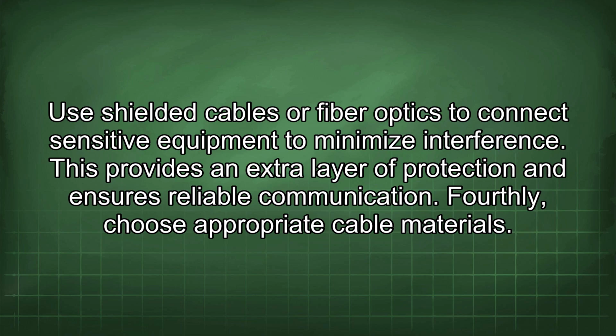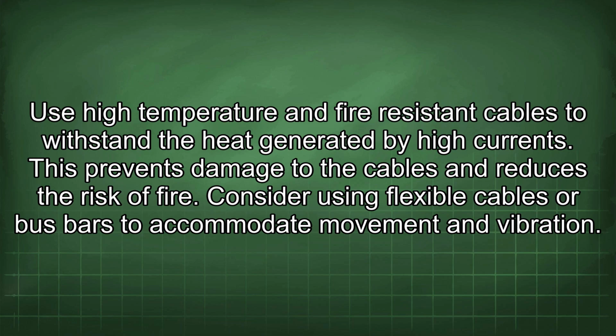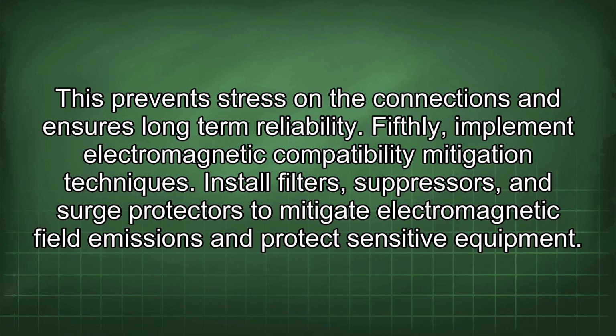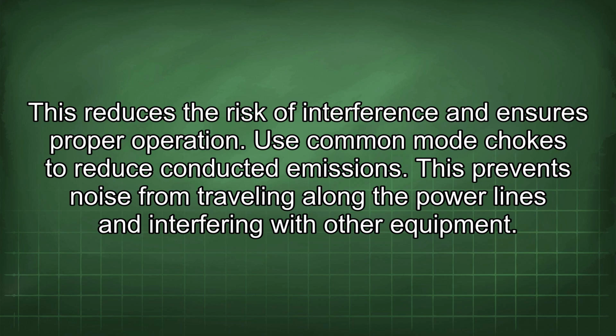Fourthly, choose appropriate cable materials. Use high temperature and fire-resistant cables to withstand the heat generated by high currents. This prevents damage to the cables and reduces the risk of fire. Consider using flexible cables or bus bars to accommodate movement and vibration. This prevents stress on the connections and ensures long-term reliability. Fifthly, implement electromagnetic compatibility mitigation techniques. Install filters, suppressors, and surge protectors to mitigate electromagnetic field emissions and protect sensitive equipment. This reduces the risk of interference and ensures proper operation. Use common mode chokes to reduce conducted emissions. This prevents noise from traveling along the power lines and interfering with other equipment.